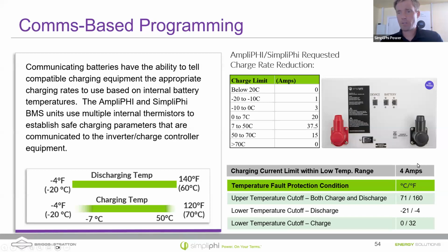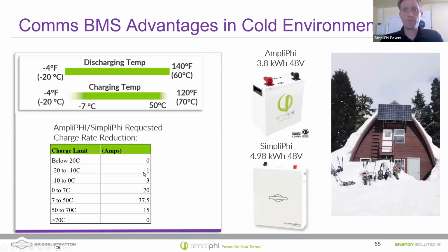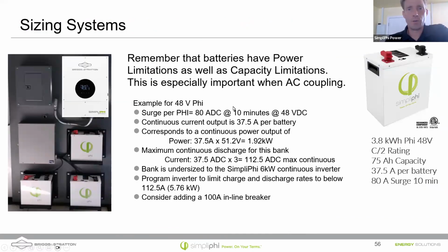If we go above a 4 amp range when we're in low temperature conditions, so 0 to -20, the battery will protect itself by opening up the contactor. If we try to charge above 71°C, it'll cut off both on charge and discharge. And then there's a cutoff there for discharge at low temperature. If we're above 4 amps at -21, it'll cut off, and similar for the charge cycle. So these are the cold weather solutions that I was mentioning to you for these communicating batteries. So if that's of interest to you, let us know.